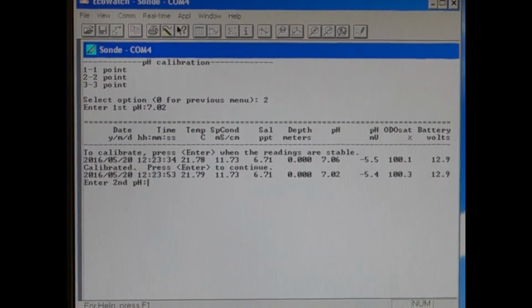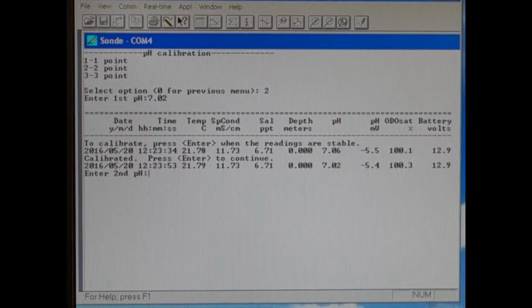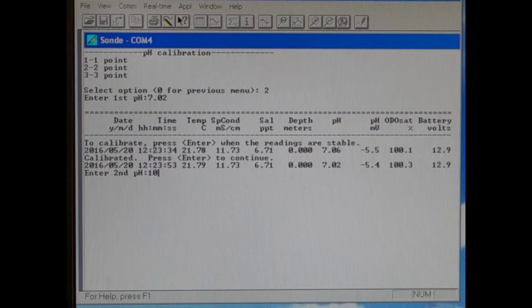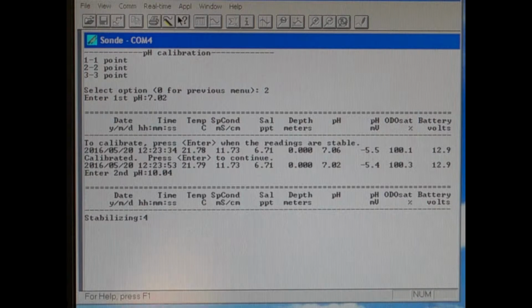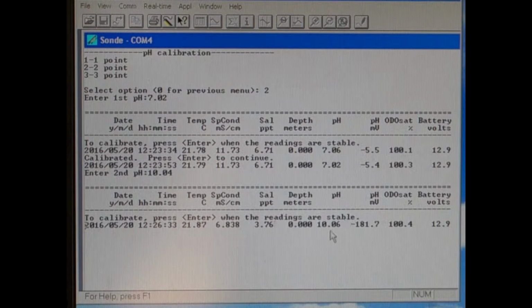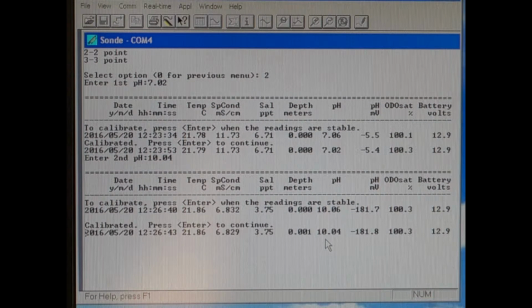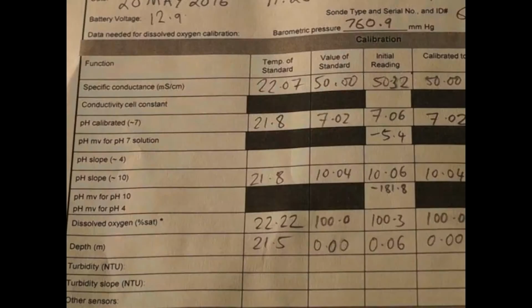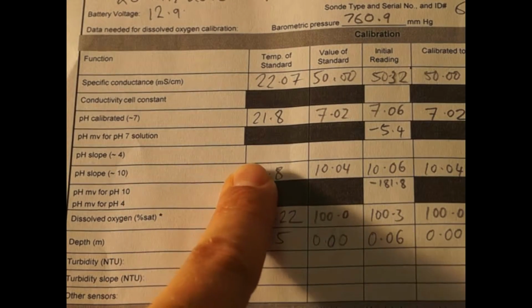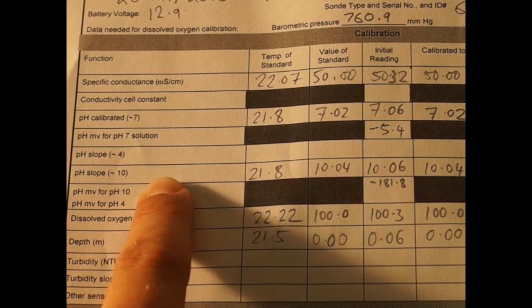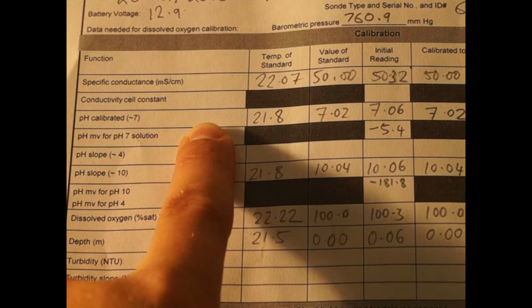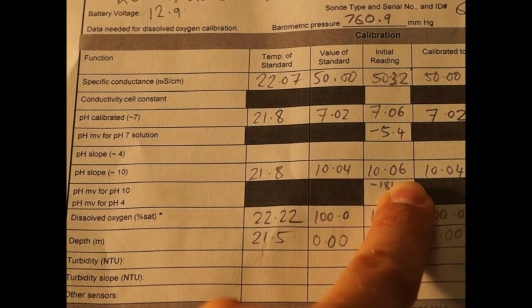Now on the computer, for the second pH, using the table from the standard, we type 10.04. We wait for the sensor to stabilize, and the initial reading was 10.06. We write that down on the calibration sheet. We push enter, and we write down the post calibration as 10.04 with millivolts negative 181.8. So back on our calibration sheet to verify, if we had done a three-way, we would have had a value for pH slope 4, but we're doing a two-way, which is the 10 and the 7. So these values are all filled out.